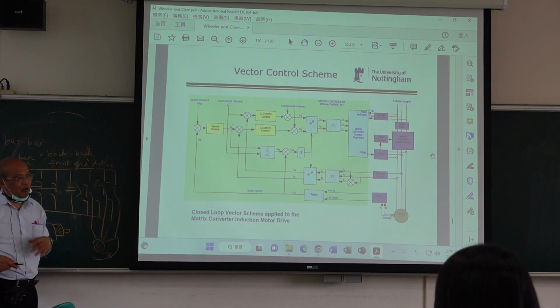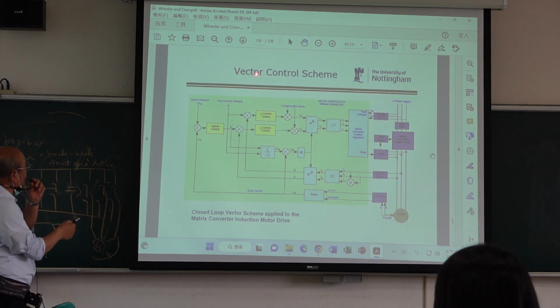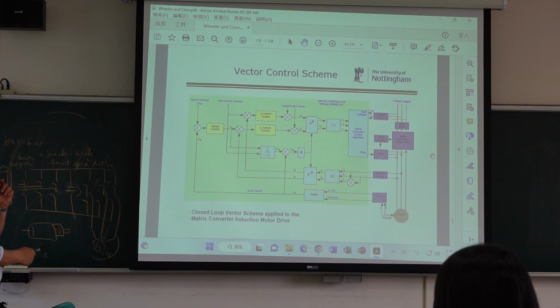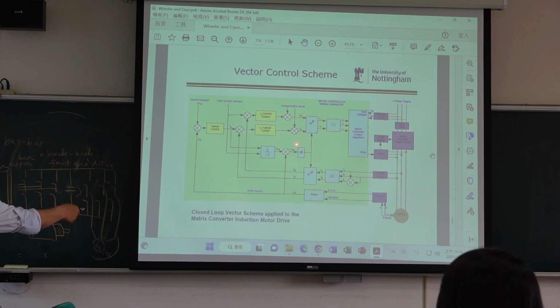So how can you control this motor? We call this field orientation control, or vector control. We have the speed command here, the feedback speed here, and then the speed error. We design a speed controller to provide the Q-axis current, and we do flux weakening to provide the D-axis current. Then we design the D-axis and Q-axis current regulators, compensate the back EMF, and provide the DQ voltage, converting it to ABC voltage to provide to the matrix converter.